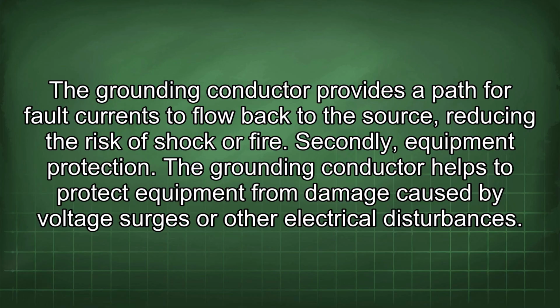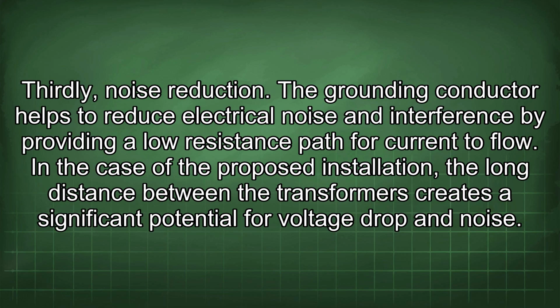Secondly, equipment protection. The grounding conductor helps to protect equipment from damage caused by voltage surges or other electrical disturbances. Thirdly, noise reduction. The grounding conductor helps to reduce electrical noise and interference by providing a low resistance path for current to flow. In the case of the proposed installation, the long distance between the transformers creates a significant potential for voltage drop and noise.